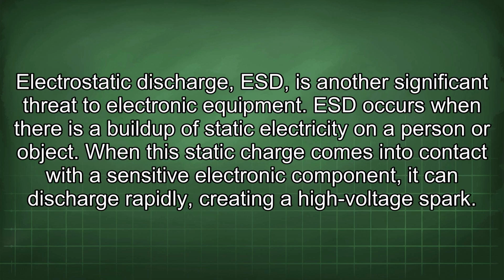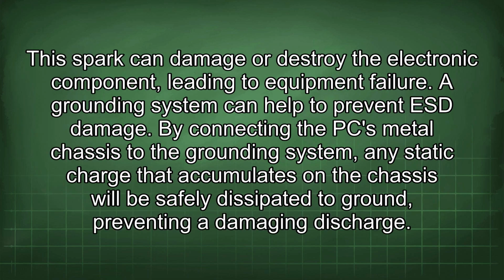Electrostatic discharge is another significant threat to electronic equipment. ESD occurs when there is a buildup of static electricity on a person or object. When this static charge comes into contact with a sensitive electronic component, it can discharge rapidly, creating a high-voltage spark. This spark can damage or destroy the electronic component, leading to equipment failure. A grounding system can help to prevent ESD damage. By connecting the PC metal chassis to the grounding system, any static charge that accumulates on the chassis will be safely dissipated to ground, preventing a damaging discharge.